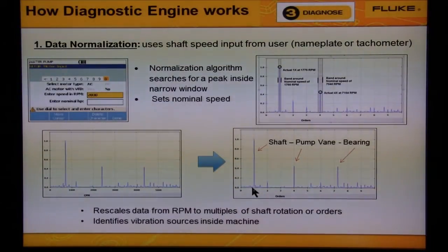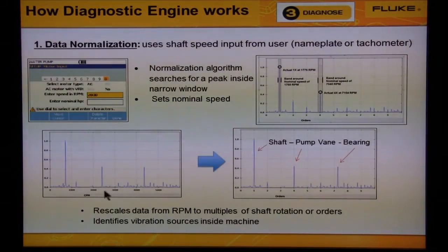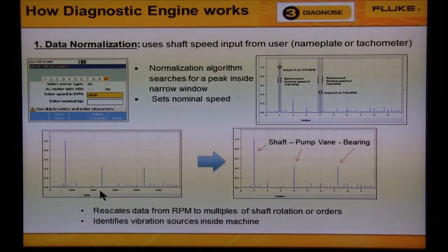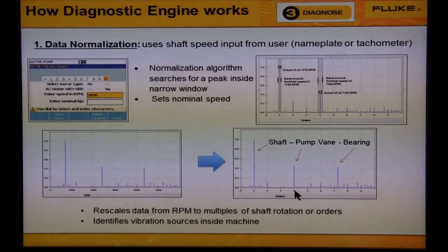It then takes information that the machine has four impeller vanes, sees a peak at 2400 in the data — which is four times 600 RPM — and identifies this as the four impeller vanes.